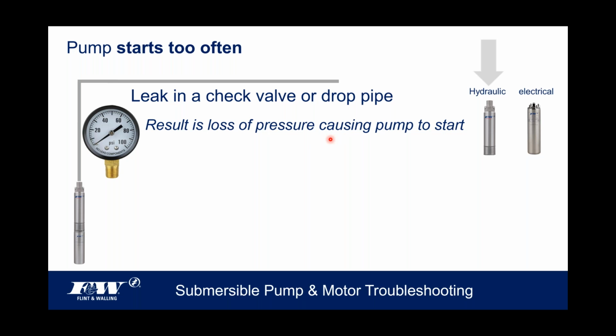So if it's not holding pressure and that pressure is slowly creeping back because of a leak, eventually, when it gets to the cut-on pressure of that pressure switch, it's going to power that pump on. Pump builds up the pressure, shuts off, and the leak's still there, so the pressure starts to drop again, and again, and again. Eventually the pump comes on, and so that could be a situation here that could be resolved by checking if there's a leak in the drop pipe, or if that check valve is actually holding down there.